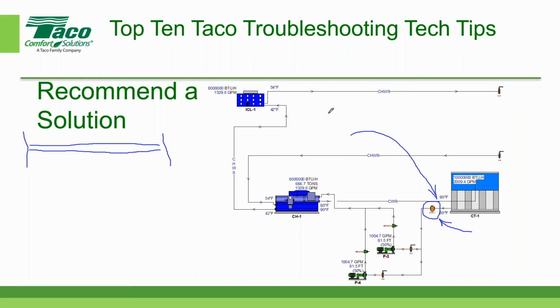I don't want to throw stones, but I would say upwards of 80 to 90% of the time, it's not a problem with the pump and it's a system issue. That's correct. The overwhelming majority of issues that we have to resolve are system issues. That doesn't mean we don't have a pump issue from time to time, but on a statistical basis. When we start the troubleshooting process, the whole process that we described here, we try not to draw any conclusions at the beginning, because it could in fact be a pump, but we don't know for sure, and that's why we have to get the rest of the data.